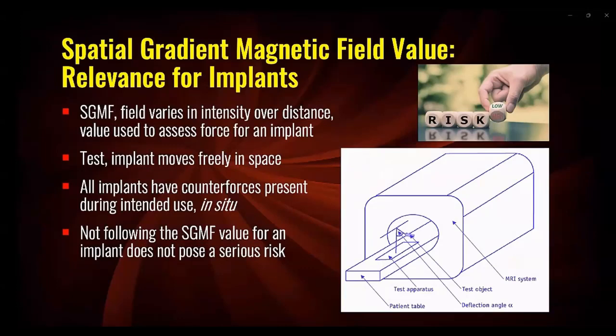It should be noted that the spatial gradient magnetic field is the field that varies in intensity over distance. When an implant is assessed for force, the test apparatus with the implant is placed at the point of the highest patient-accessible spatial gradient magnetic field.